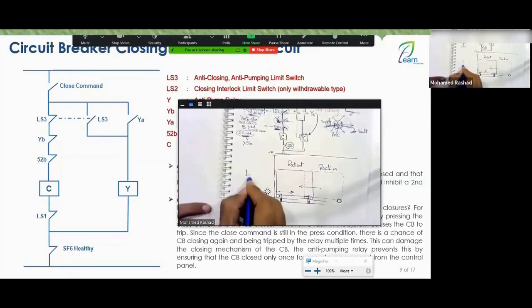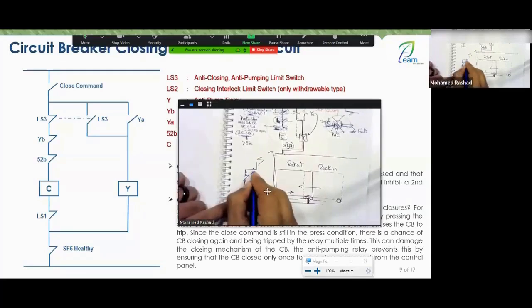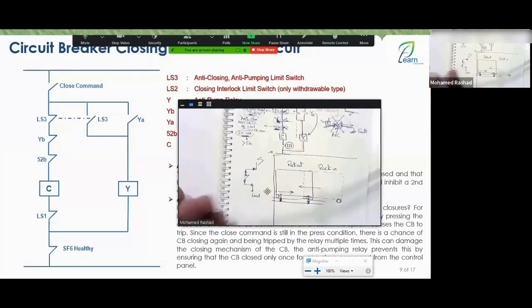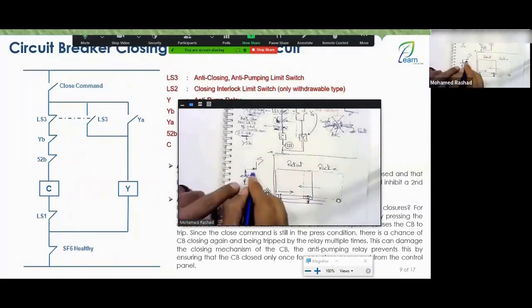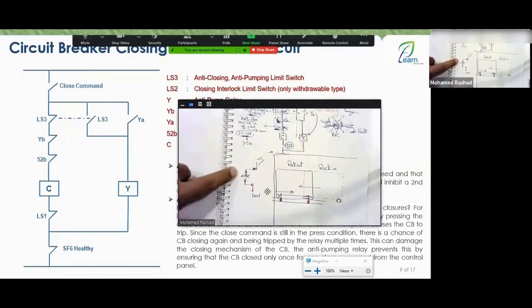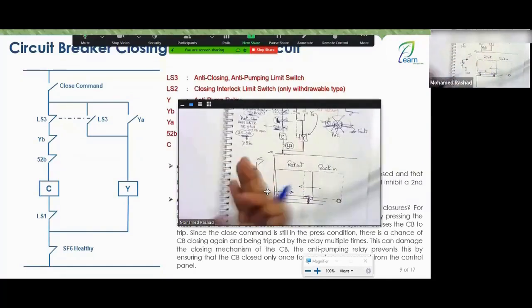Because engineer, you can't have your electrical breaker closed like this and then try to rack it in. Well, here there is a supply and here there is a load. You can't do that. As you bring the breaker closer to the supply and load, an arc or spark will occur here. That's why you must insert the breaker, rack in, and then close the electrical breaker. At the same time, you can't have it closed and pull it out because a spark will occur here, and a very large arc could happen, which might explode. That's why you must first open it, then pull it out, rack out.